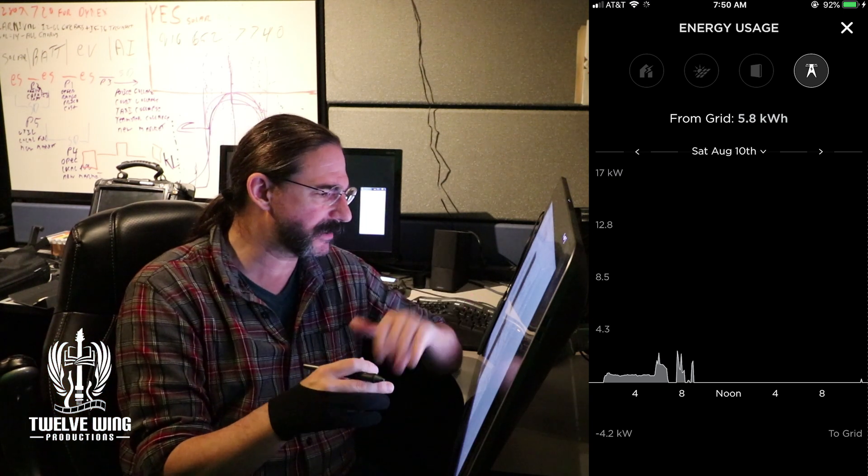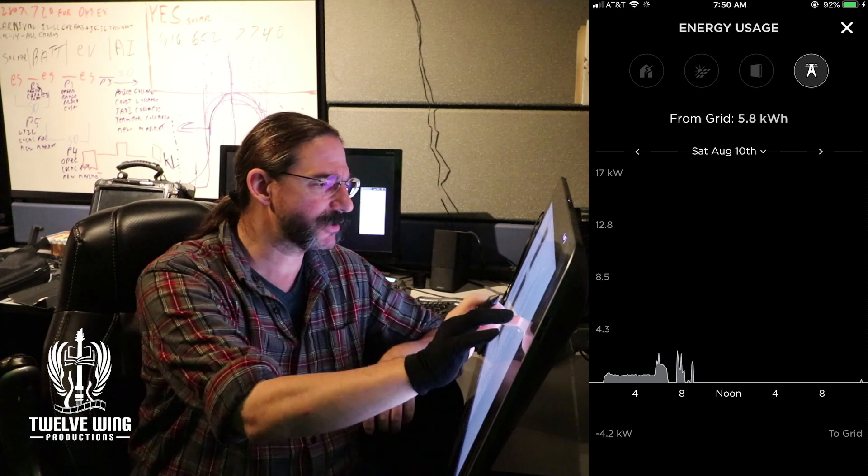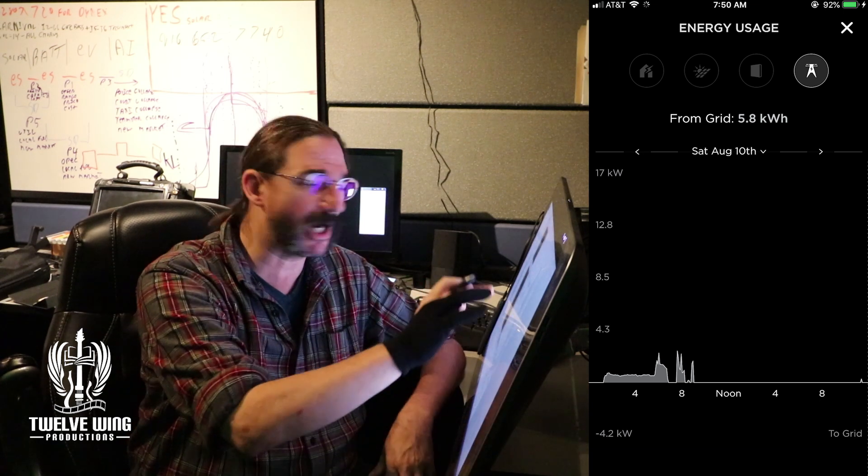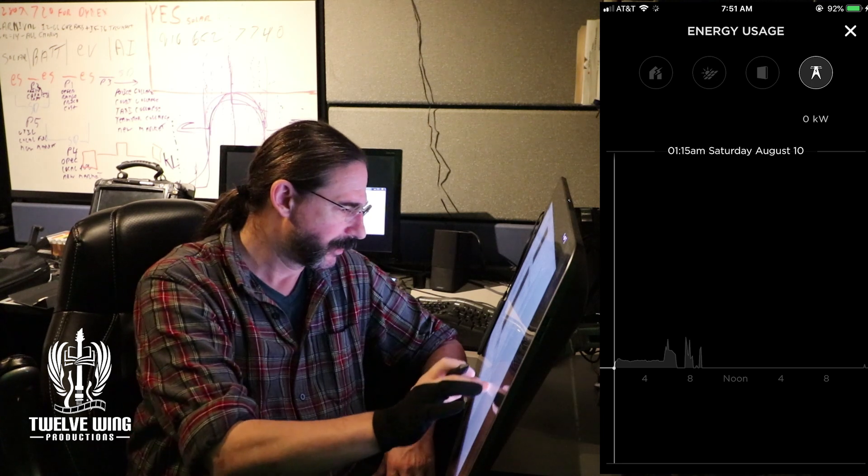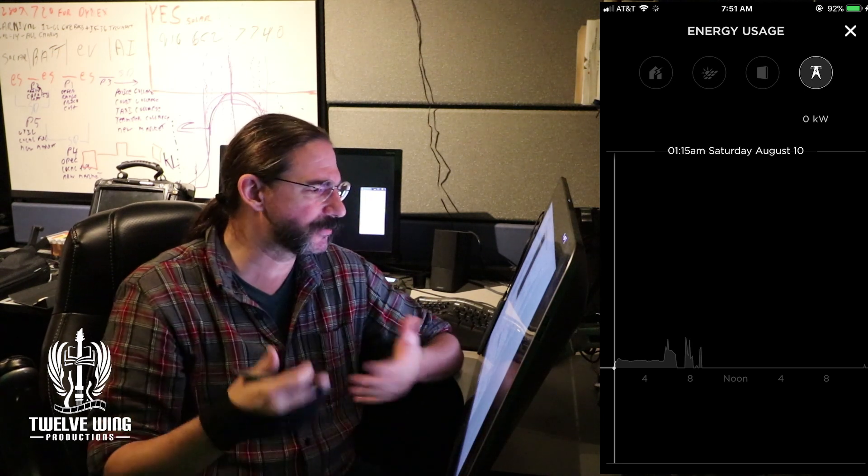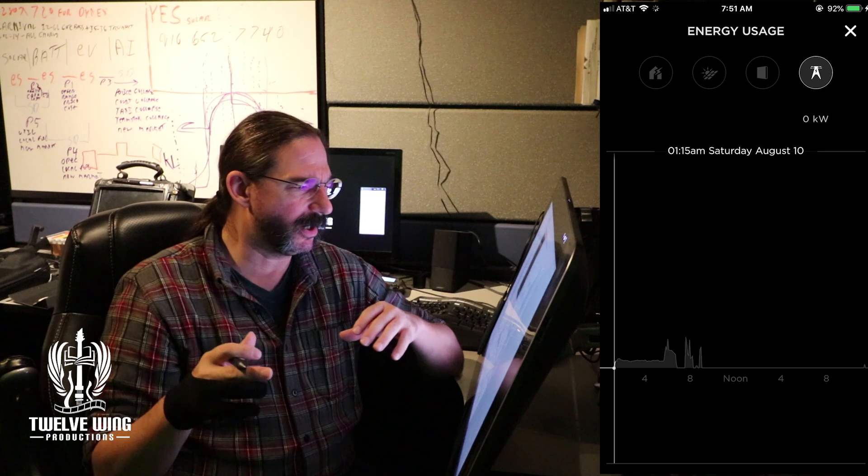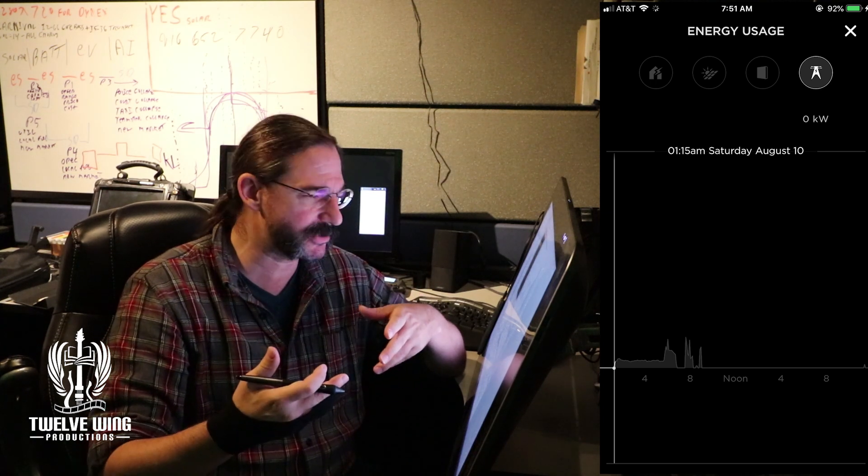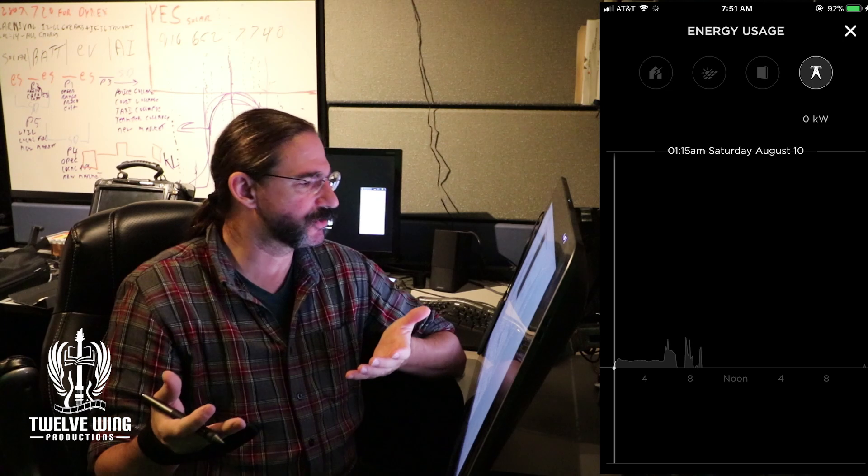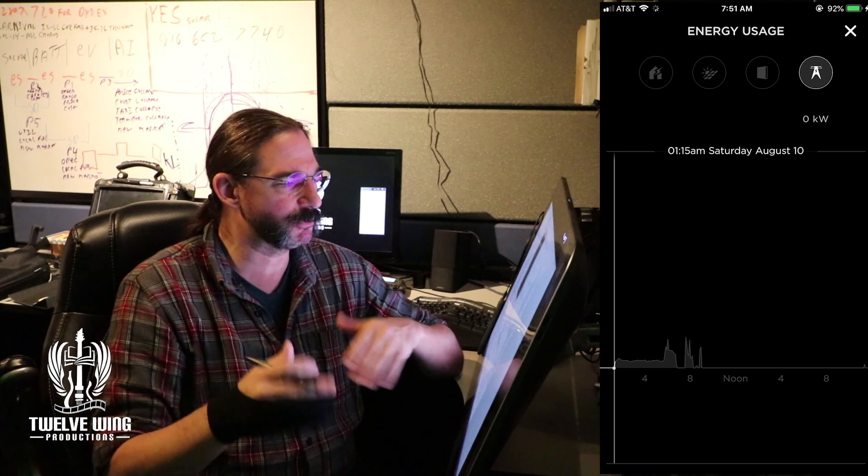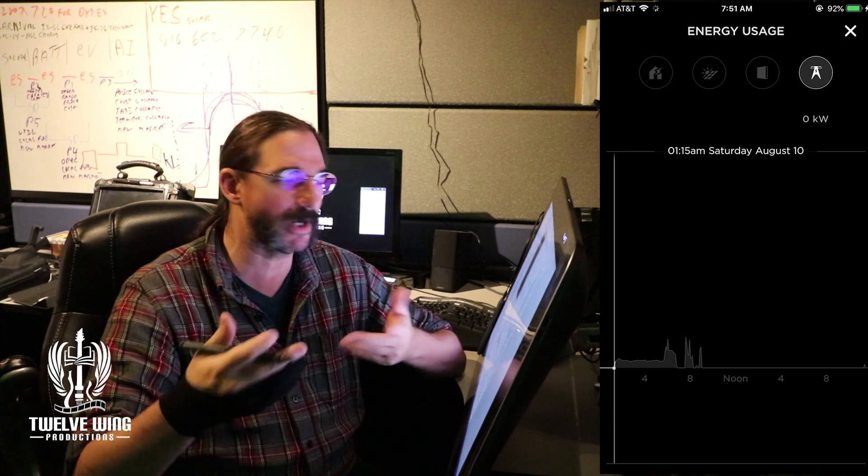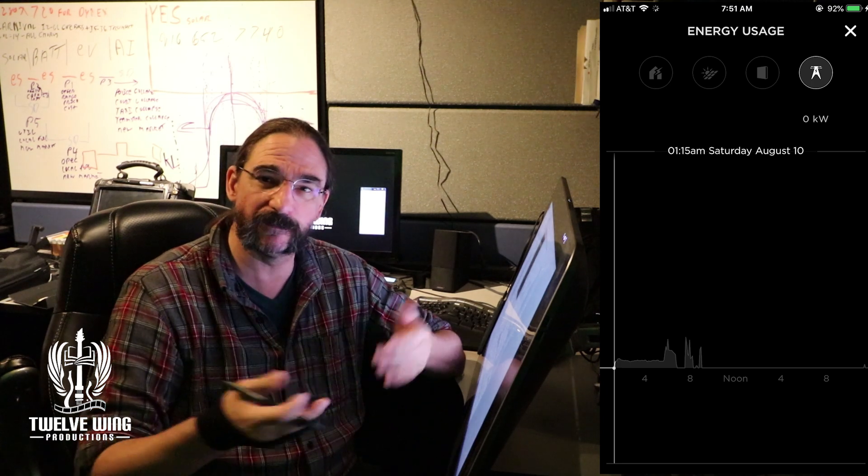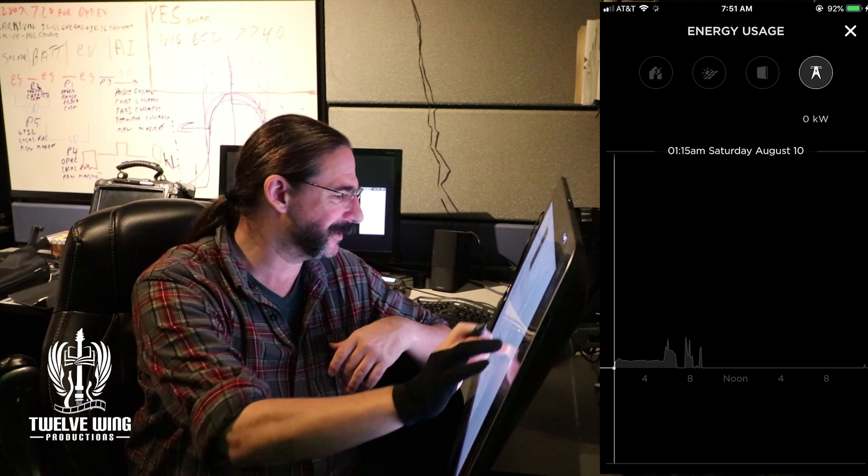And so by touching the screen, you can actually get a report of exactly what time the battery was depleted. That's useful when you're trying to make decisions on things like how much reserve you want to leave in your system. Reducing your reserve setting slightly might make the difference between making it until morning or having to draw a little bit of power off of the grid.